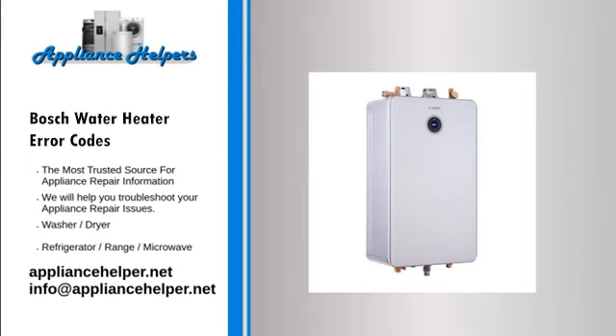Code E9. Problem. Overheat sensor ECO has an open circuit. Fix. Check the wire connections on the sensor and control board. Ensure the venting system is per codes and instructions. Descale the unit if necessary.